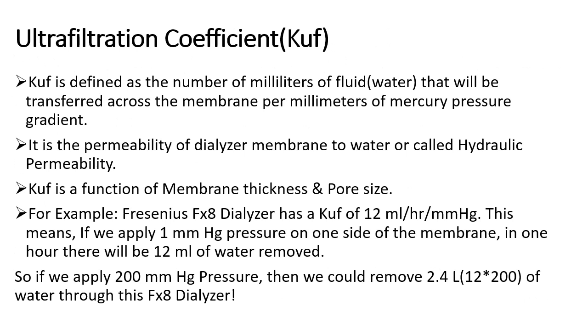The next characteristic is ultrafiltration coefficient, or KUF, also known as the hydraulic permeability of the dialyzer — that is, how effectively a membrane can allow the transfer of fluid or water according to a given pressure. KUF is a function of membrane thickness and pore size. For example, the Fresenius FX8 dialyzer has a KUF of 12 ml/hr/mmHg, meaning that applying 1 mmHg of pressure across the membrane for one hour will remove 12 ml of water.